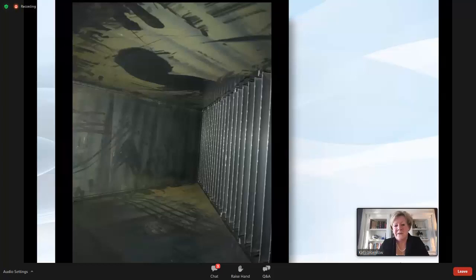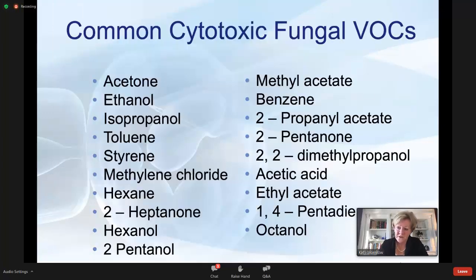This is an image taken by my colleague. This is downstream of the final HEPA filter serving the IVF laboratory, downstream. So there is nothing between this air and the laboratory. And if you look at this effervescent glow here, that's Aspergillus. That's a fungal spore. And again, downstream of their final filter. Why is this of a concern? Because fungal spores are a great source of fungal VOCs. And this is a short list, all cytotoxic. So it's critical to remediate your fungal microbial spores.